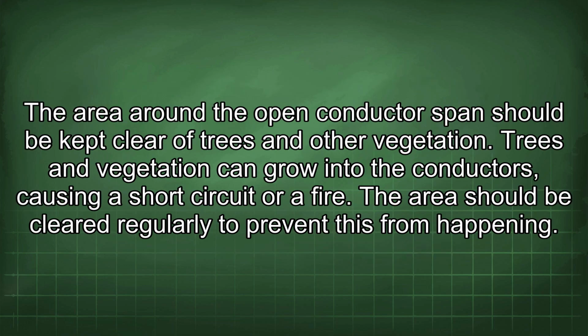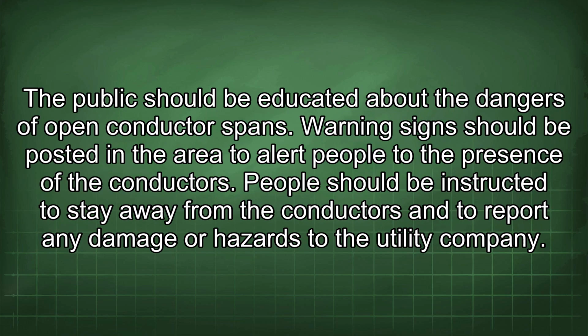The area around the open conductor span should be kept clear of trees and other vegetation. Trees and vegetation can grow into the conductors, causing a short circuit or a fire. The area should be cleared regularly to prevent this from happening. The public should be educated about the dangers of open conductor spans. Warning signs should be posted in the area to alert people to the presence of the conductors. People should be instructed to stay away from the conductors and to report any damage or hazards to the utility company.